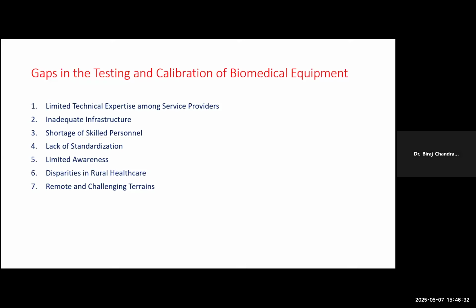There is no proper ventilation. There is no proper maintenance of temperature and humidity. Sometimes the temperature is maintained but humidity is high. So ultimately, the efficiency of the equipment will be lower, the result will be poor, and indirectly it will hamper patient safety. Then lack of standardization and limited awareness about the maintenance and calibration of equipment. It may happen that the top of the institute may not have the idea that calibration is also an important aspect of the equipment for getting the correct result.